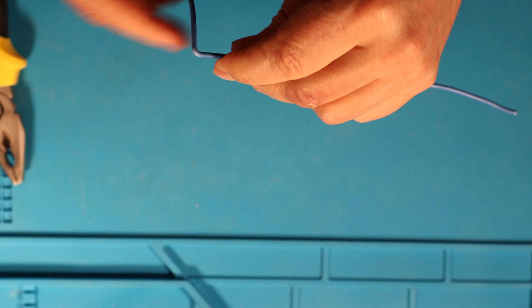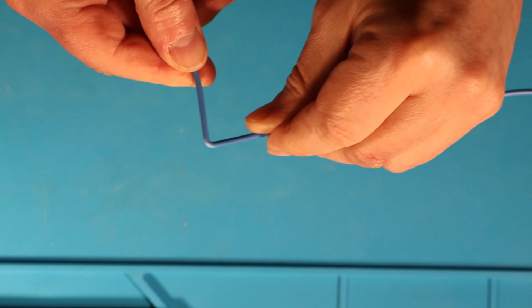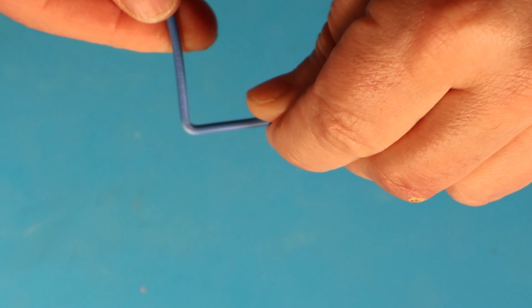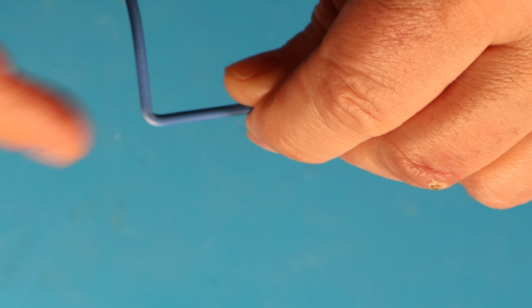But why does such a thing exist? The reason is that if you bend a cable too tight, you create stress in the structure of that cable, both in the conductor and in the insulation. There are two main implications of the requirement for a minimal bending radius of a cable. The first one concerns laying out cables, and the second one regards making cable connections. Let's have now a closer look at each one.